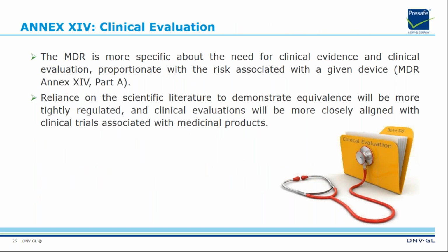Annex 14 is about clinical evaluation. The MDR is more specific about the need for clinical evidence and clinical evaluation, proportionate with the risk associated with the given device. So reliance on the scientific literature to demonstrate equivalence will be more tightly regulated, and clinical evaluations will be more closely aligned with clinical investigation and clinical trials associated with medicinal products.